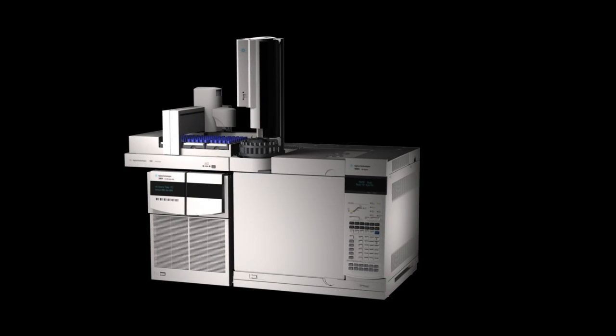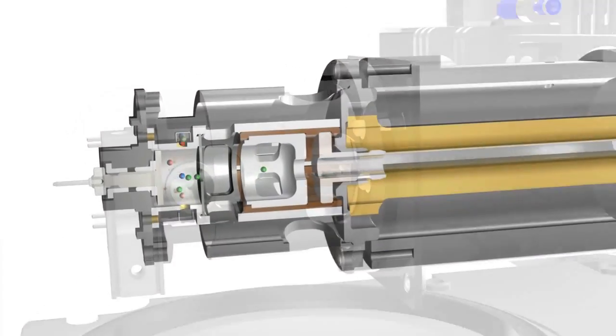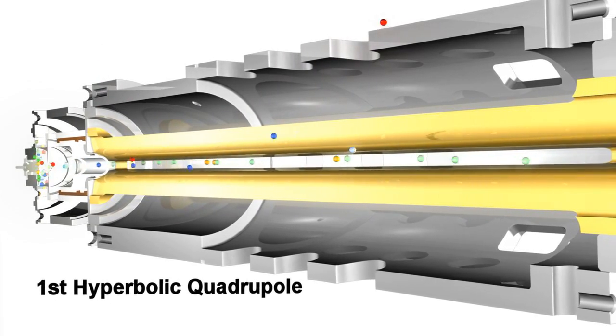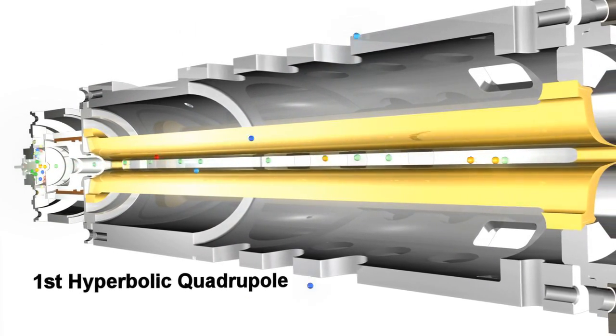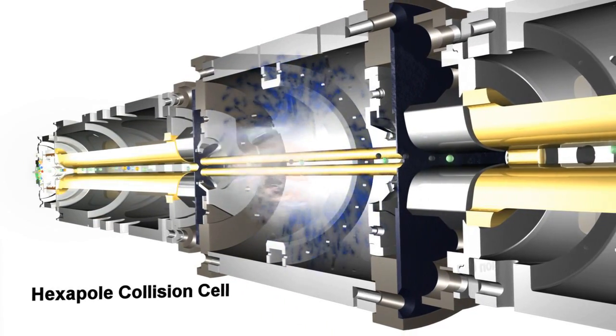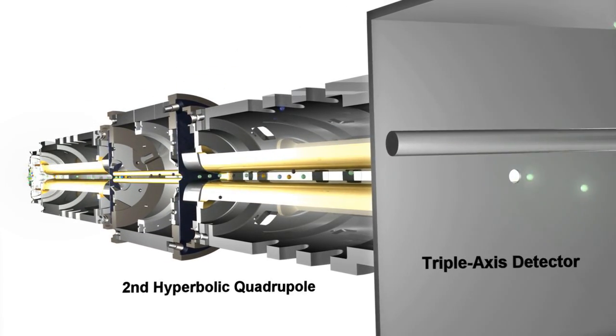The typical MS-MS description focuses on the extraction of ions from the source, isolation of the precursor ion in the first quadrupole, dissociation of precursor ion in collision cell, and mass filtering of the product ions in the second quadrupole before detection.